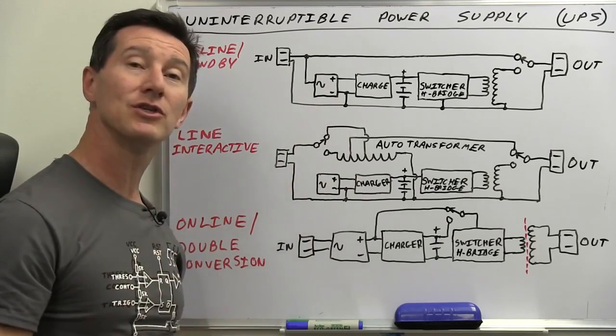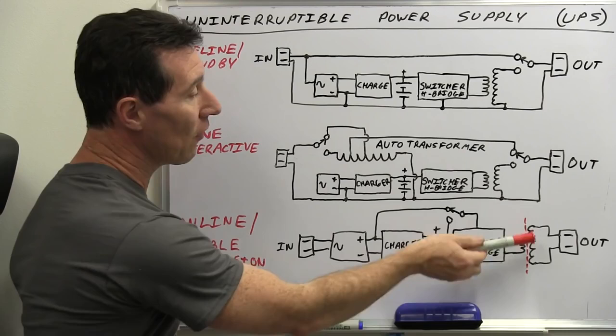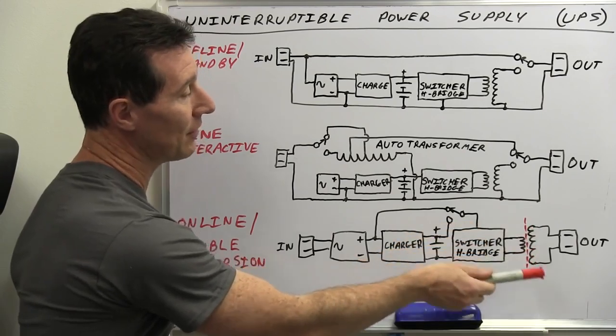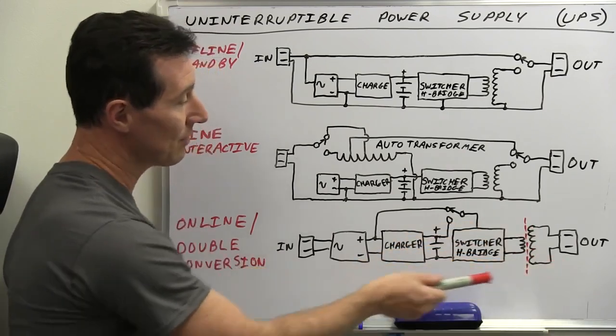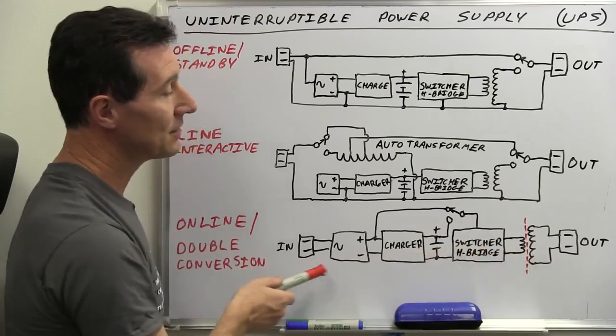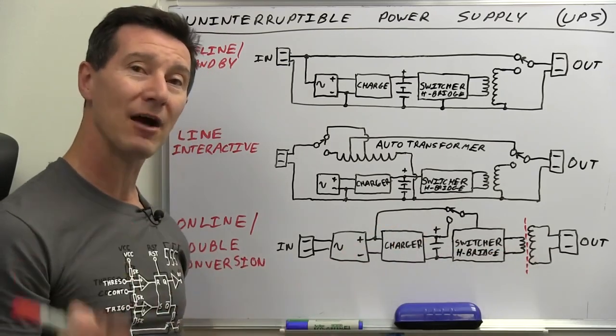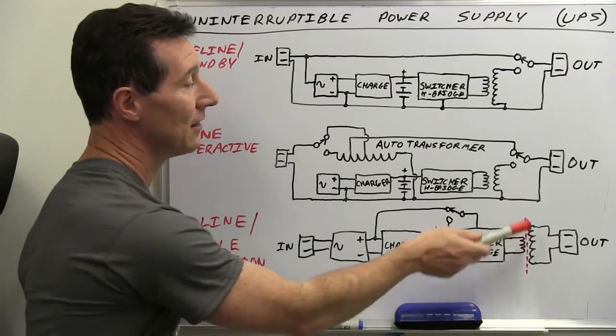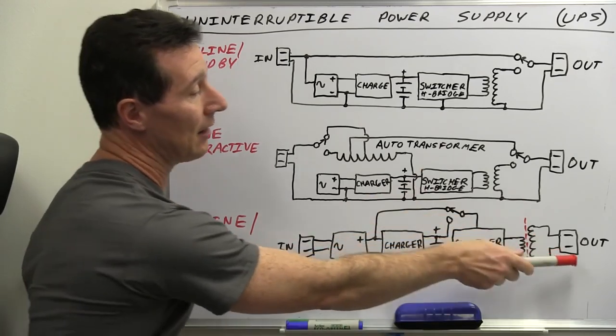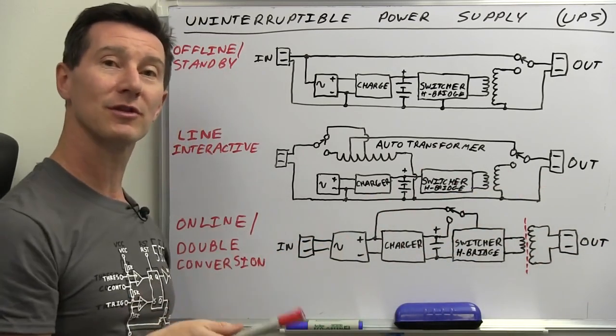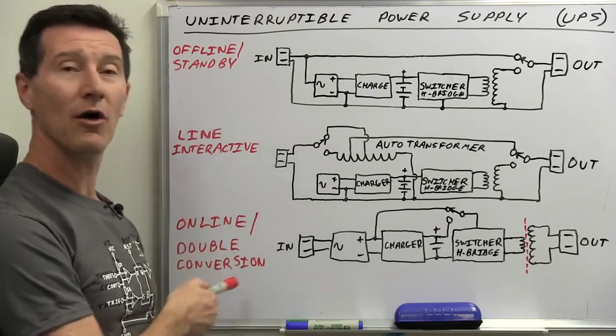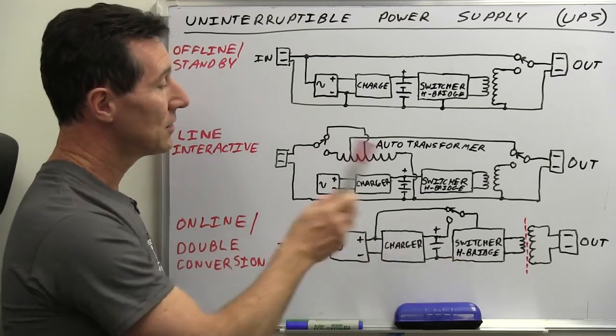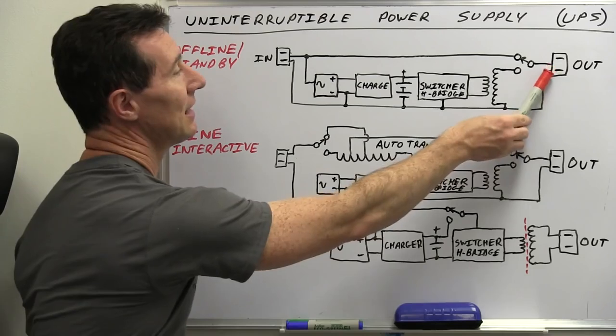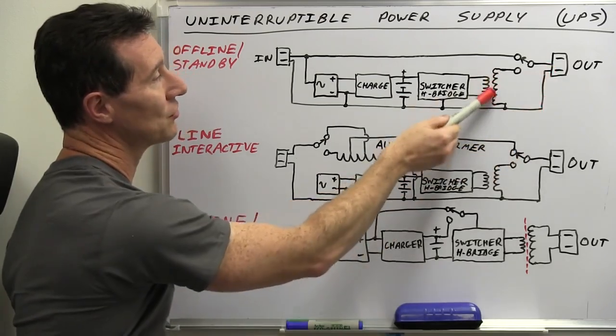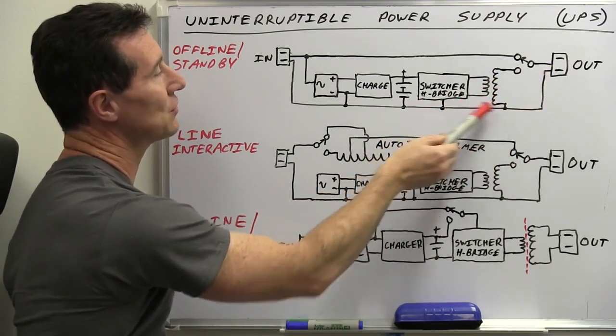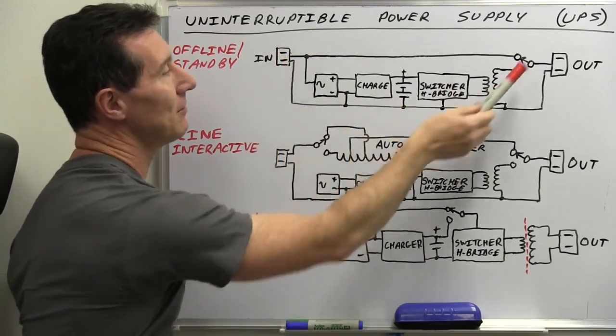One of the main reasons you want to do it is for isolation. You'll notice there's no direct electrical connection from the output to the input -- it's galvanically isolated. So if the device you're powering needs to be electrically isolated from the input, then an online, or double conversion, switcher is the way to go. But as you can see here in the offline type, there's no isolation -- even though there's a transformer, it's all commoned from the input to the output.